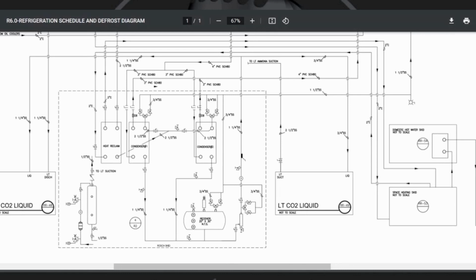Hill has been a big proponent of thermal siphon CO2 cooling. These two happen to be built by Zero Zone, and they're a big proponent of it also. But it is extremely inefficient because you have to run those plate heat exchangers at least 10, in our case 13 degrees colder than you want the liquid CO2 to be, to make it condense on the plates. What kind of superheat are you running on the ammonia side in order to achieve that 11 or 12 degree TD that you were talking about? We only have about 5 or 6 degrees of superheat. Oh wow. It's really close.